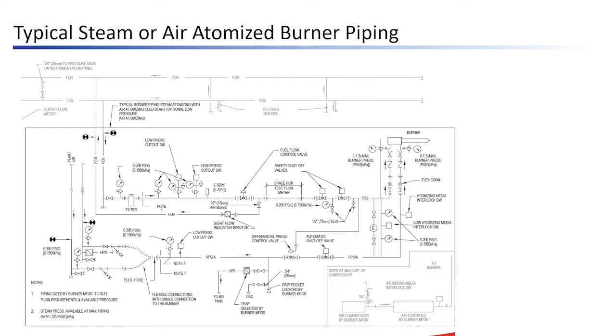This one has plant air on the left-hand side to the left and parallel to the steam. So I think this was a VA hospital project, and it looks like it's set up for atomizing air or atomizing steam.